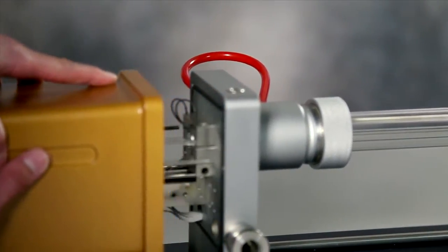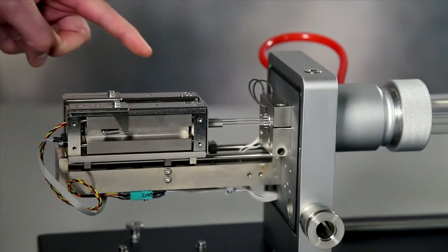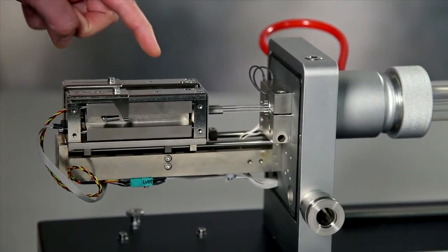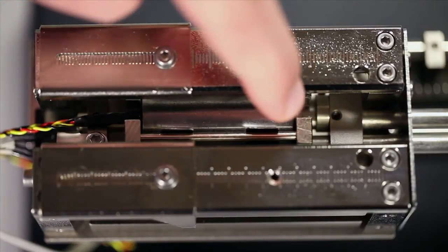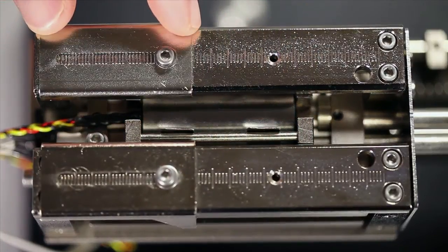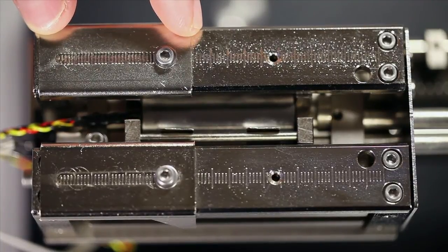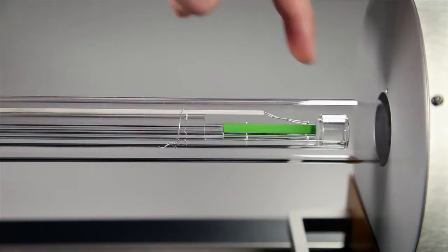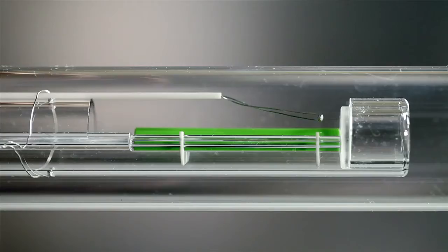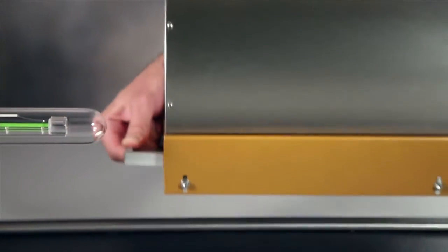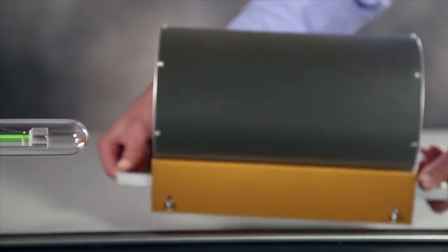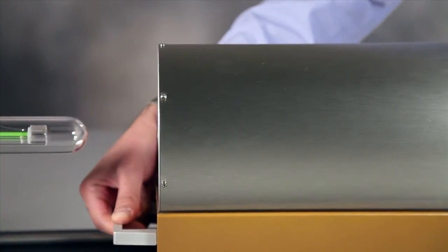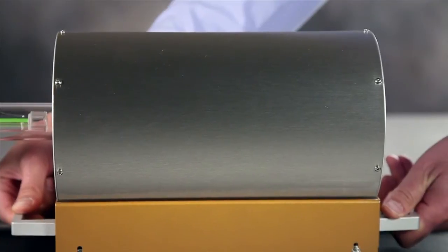It has three main components. The measuring head is thermally stabilized and has a state-of-the-art LVDT for precise dimensional measurements. It also has an adjustable contact force up to 1 newton. Sample holder and push rods support the thermocouple and the sample. And a modular furnace that is easier to change to cover the widest temperature range.